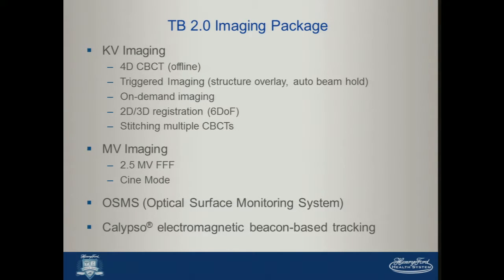In terms of KV imaging, there's 4D CBCT, which is new, but though you can acquire a 4D CBCT at the time you treat the patient, it can be reconstructed and viewed offline. It can't be used online. There's a number of options for triggered imaging, and I'll show you more of those. On-demand imaging, which doesn't have to be pre-configured. You can interrupt the treatment at any point and use one of the on-demand imaging options to verify patient setup. 2D, 3D registration now instead of the previous 2D, 2D registration, which we found very helpful.